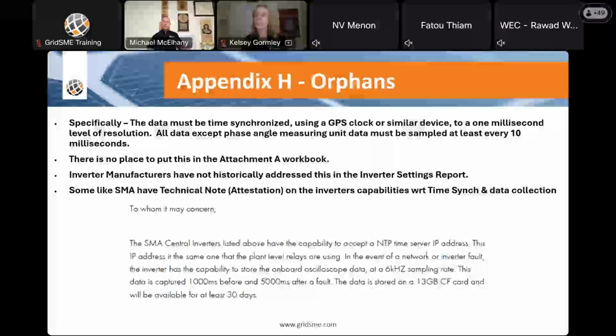And then there's a couple of orphans, and it was near the end of Kelsey's part of the presentation where she talked about the GPS clock time syncing to 1 millisecond, and that you have to have data sampling for every 10 milliseconds. There's no place to put this in the attachment A workbook. It's not historically been addressed in the inverter settings report. There might be an inverter settings report where it makes a reference to network time protocol, but it doesn't give any sort of capability of the inverters to be time synced at 1 millisecond and actually collect the data, sample the data every 10 milliseconds.